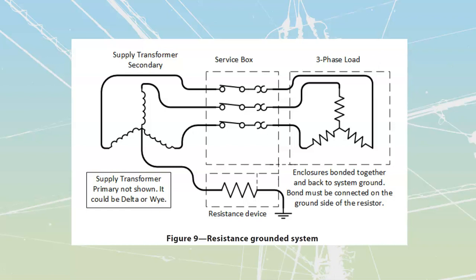Systems we've looked at so far had massive amounts of current, but now we're going to work on systems with a neutral at a much higher voltage. Remember, any system from 30 to 750 volts has to be solidly grounded at the neutral. But once we go into higher voltages, we sometimes don't want to do that, because a fault would be so violent there's a much greater chance of massive destruction of components and risk to electricians, plant operators, and people in general.